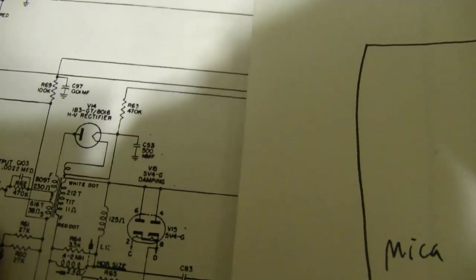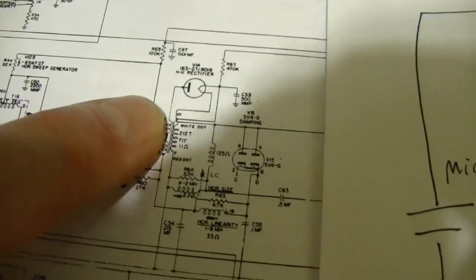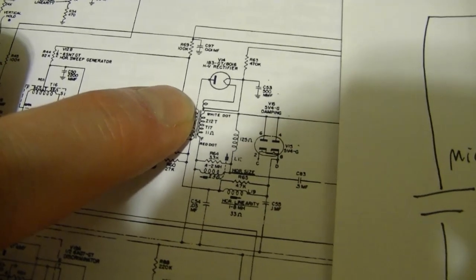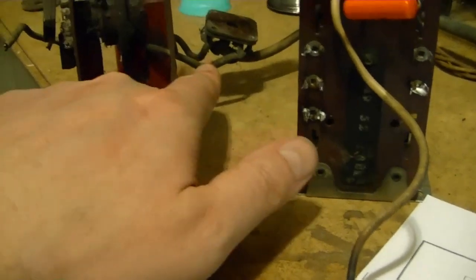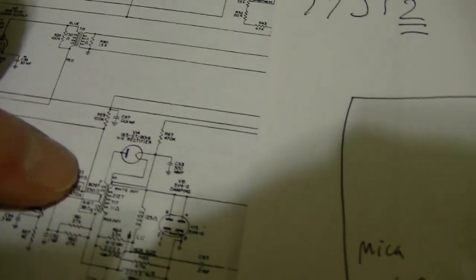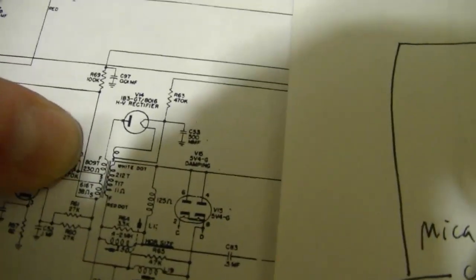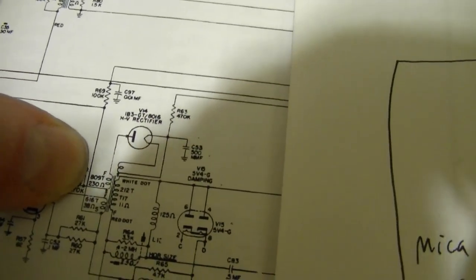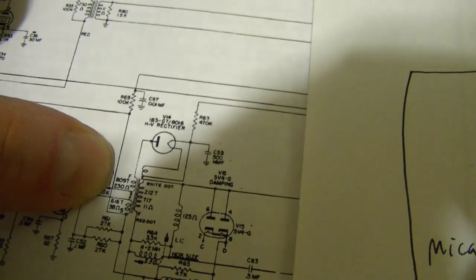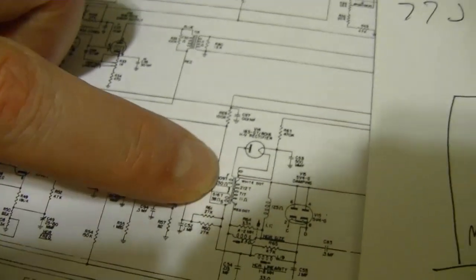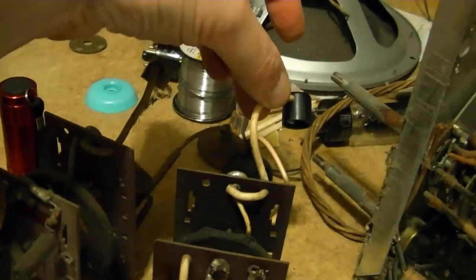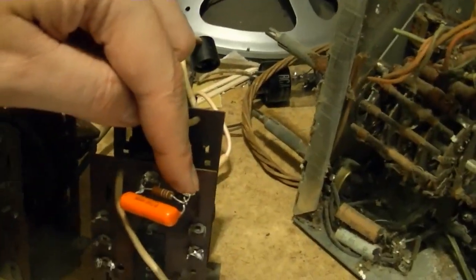If you look at the schematic, we have a total of 4 coils. One filament for the high voltage tube, that's just a loop of wire, a piece of cake. Another, the one that says 809T 230 ohm, means 809 turns, 230 ohms resistance. That's the high voltage winding, and that's this guy and this lug here.